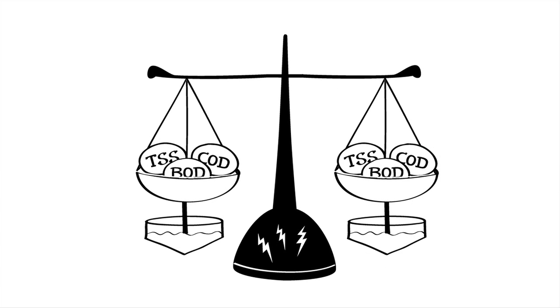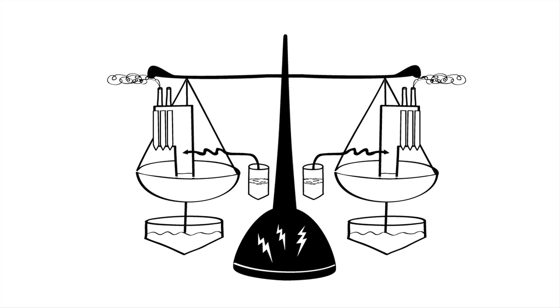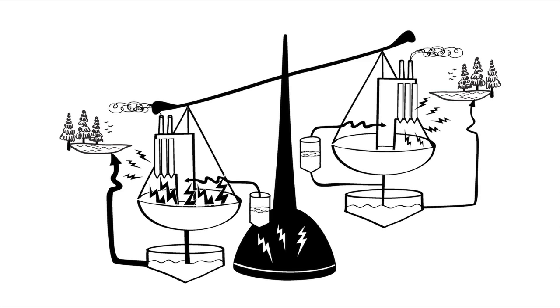Let's talk about BOD, COD, and TSS trade-offs and co-benefits in relation to energy. Source reductions of BOD, COD, and TSS within the manufacturing process, which capture energy from otherwise lost raw materials, for example by reducing unintended losses of pulping liquor, offer energy savings made all the greater by not having to supply energy to manage them as wastes or wastewater.